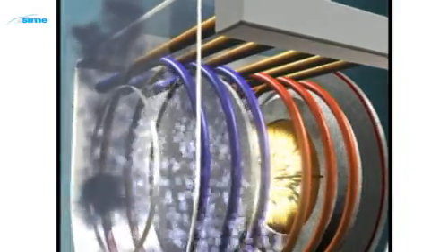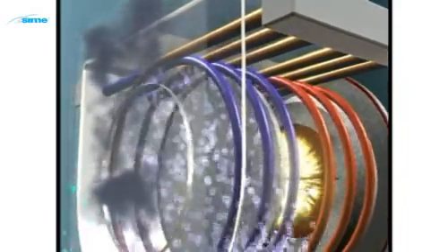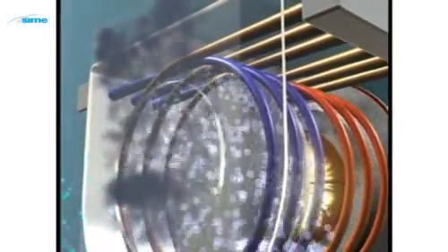Unused heat then passes through the rear section of the coils, preheating the system water as it enters the heat exchanger. This is where most of the condensing occurs, producing a majority of the condensate.